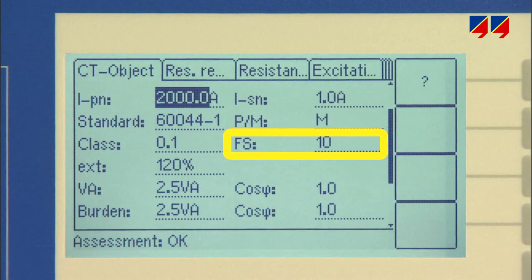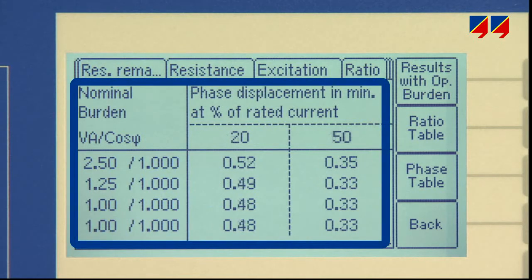It shows the instrument security factor at the actual burden, verifying the meter's protection against overcurrent. Amplitude and phase error can also be calculated for any combination of primary current and burden required by the user.